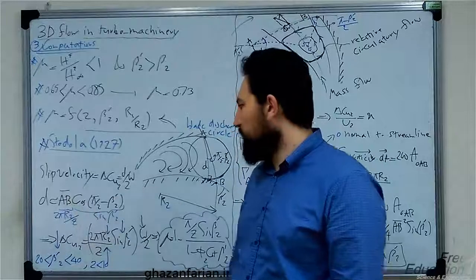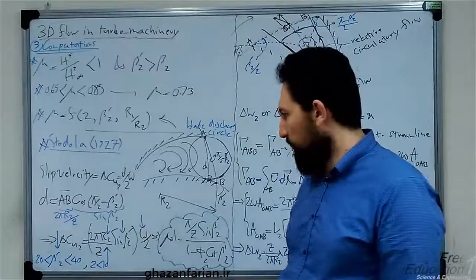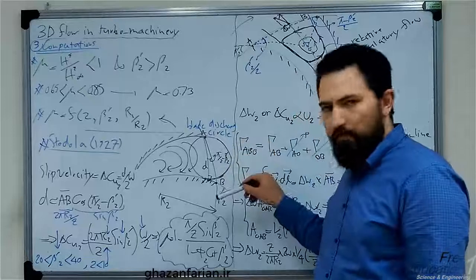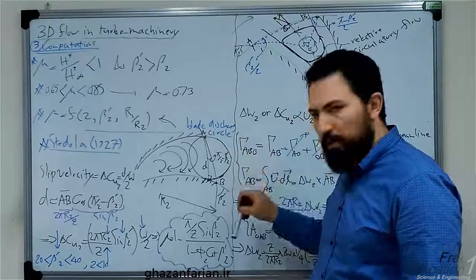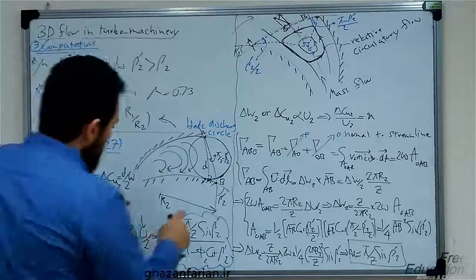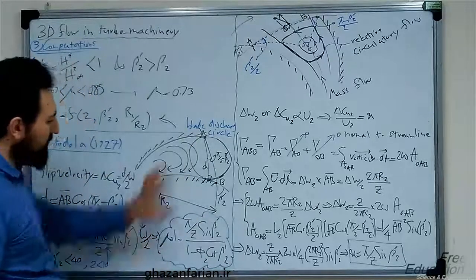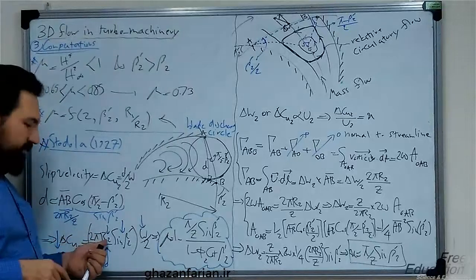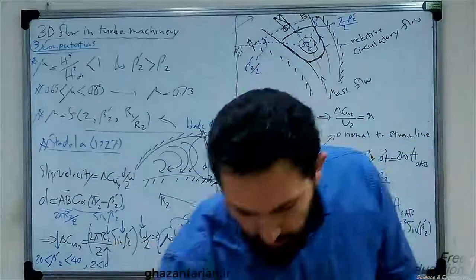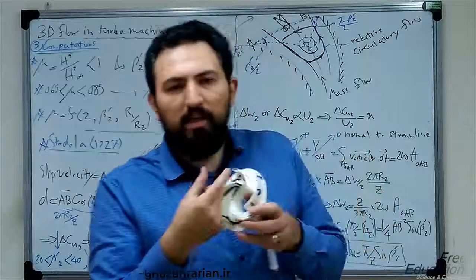In the slip velocity relation, d is an unknown parameter, so we approximate d as follows. The line AB is part of the circumferential circle of the pump. The radius at the outlet is R sub 2, so the length of this arc is 2 pi R sub 2 over z, where z is the number of blades. With five inter-blade spaces, AB is the length of one segment of the circle, equal to 2 pi R sub 2 over z.